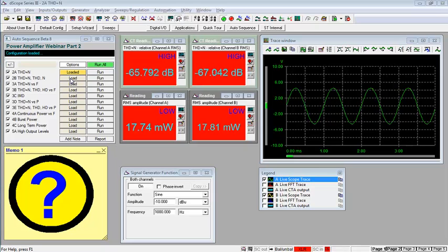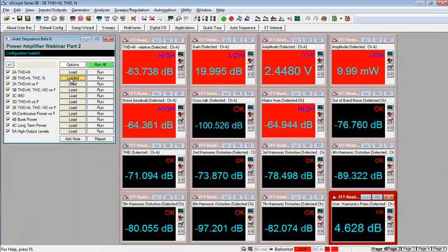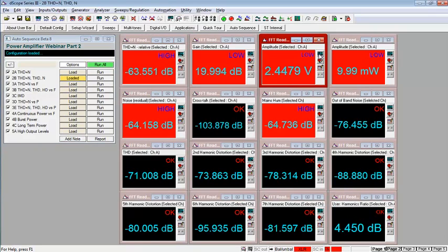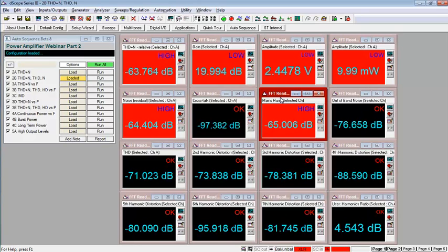And for that, I'm going to load a different test from my sequence editor here. And in this test, I've got far greater levels of detail in the analysis. So I've got some rather interesting and unique tools here that we refer to as smart FFTs, or FFT detectors more formally, and these are giving me lots of different numerical readings. How are they obtaining them?